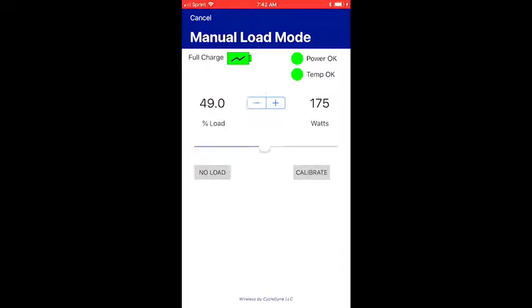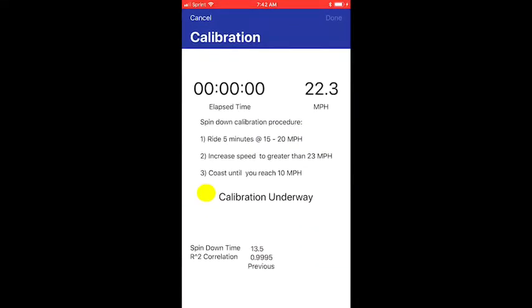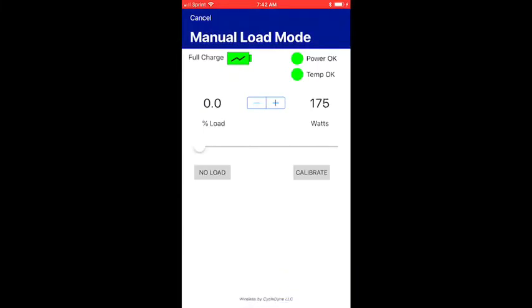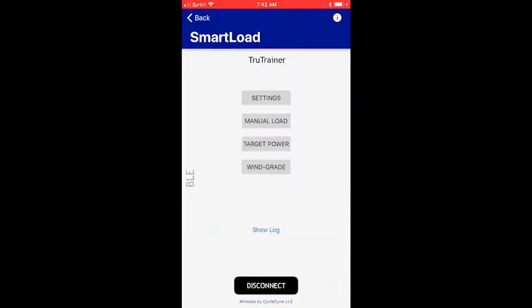You will have noticed, though, that to perform a calibration, it has to be done with the servo controller of the TruTrainer at no load conditions. So we automatically drop that to the no load position when we go into calibration, as evidenced by it's at the 0 load position when we come out of the calibration mode. So to get out of manual mode, you go up to the top and press the cancel, which brings you back to the home screen. I'm going to go in and talk about target power now.